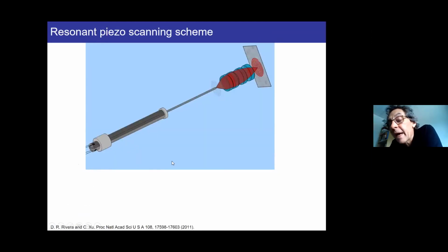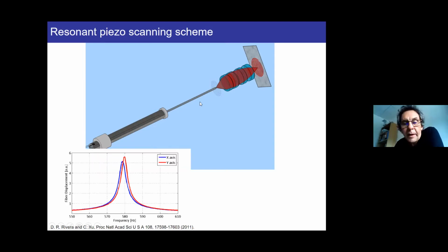So it's just like a confocal microscope, but it's a tiny system. And the scanning mechanism that we are using is actually not a raster scanning, that makes a zigzag in a conventional microscope. In this case, it's more like a spiral. It means that the tip of the endoscope will make an increasing spiral from which we will excite the sample and we will collect the signal.